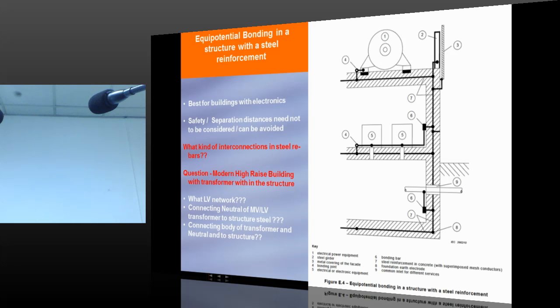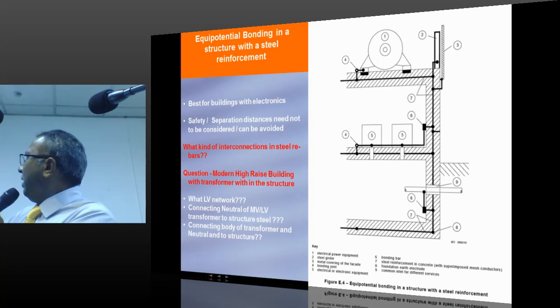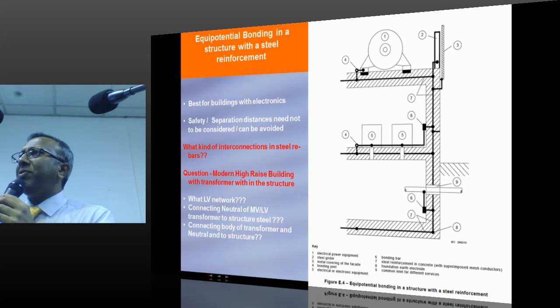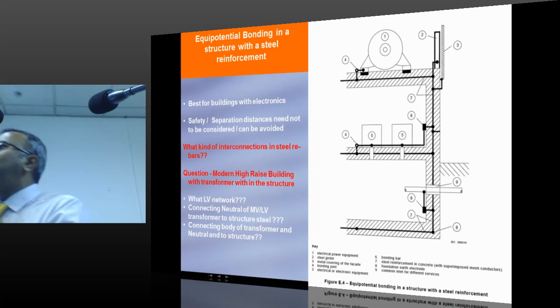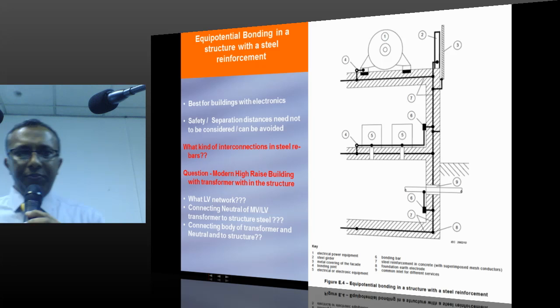One of the ways you connect it together so that there is no flashover. Number 2 is you keep it away from the lightning protection system. You calculate the safety distance, the separation distance required, and you keep it away. So now the point for you is, if you make use of this steel reinforcement, you can just avoid the safety distance. You don't need to calculate. You don't need to complicate the total design.